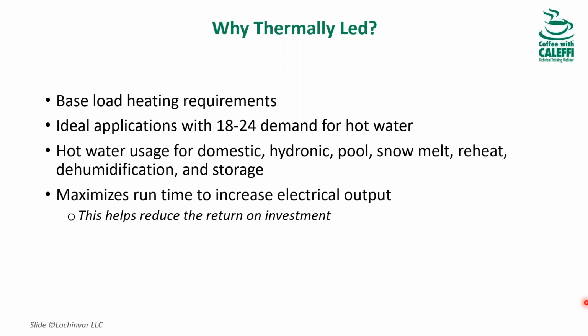Okay, so we want to base load that heat. We want to take that 163,000 and find applications where we have a constant demand for it. Now, if we have other applications that we can use that heat for, say overnight, we put it into a brazed plate heat exchanger and do a pool. We can do snow melt, reheat, dehumidification, storage. It helps improve the runtime, and this helps reduce the return on investment.